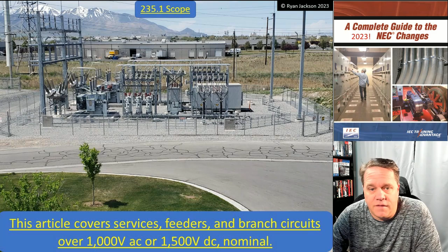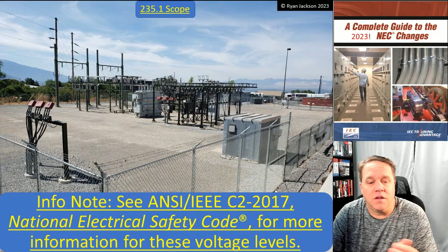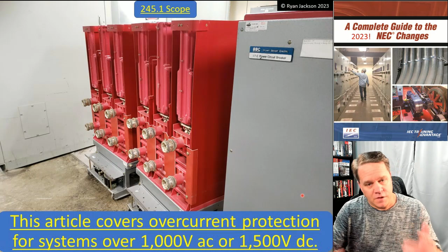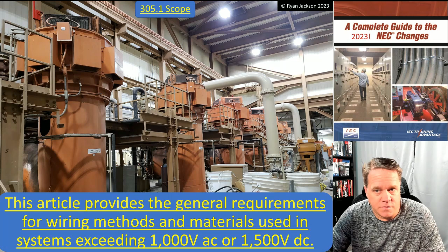It says, look, take a look at ANSI IEEE C2 2017 edition, which is the National Electrical Safety Code, for more information on these voltage levels. This is what the utilities follow. Even if you are an NEC regulated installation, if you're doing this kind of work, you're going to need to bring in the National Electrical Safety Code as well. Article 245, as I mentioned, is overcurrent protection for over 1,000 volts. So if these massive rack-in power circuit breakers, vacuum circuit breakers, are your world, then this is where you'd find it. And then Article 305, general requirements for these medium voltage, higher voltage installations.